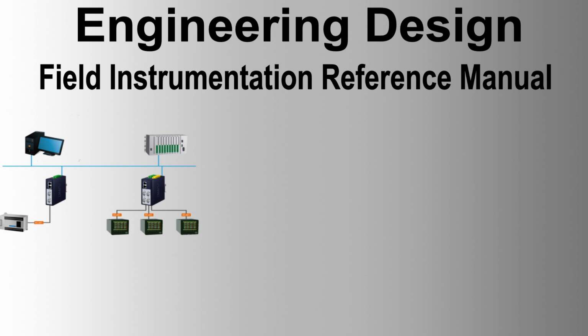Local panels and cubicles. Local panels should be avoided unless approved, and materials and paint systems should be suitable for the intended location. Instruments and local panels should be mounted at eye level and protected from steam outlets and water. Installation notes. Inline instruments should be installed by the mechanical engineering discipline under the supervision of the instrument engineering discipline.